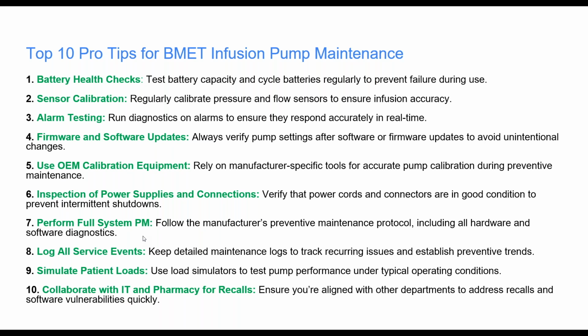Simulate patient loads. Make sure that when you are looking at devices, especially those that are questionable, right? Somebody's had a question about it. You may want to have more of an approximation about what they were running. And this goes for pretty much any device. Simulate the patient, or the conditions, and see if you can get it to fail or find the root cause of a problem or rule out the problem.